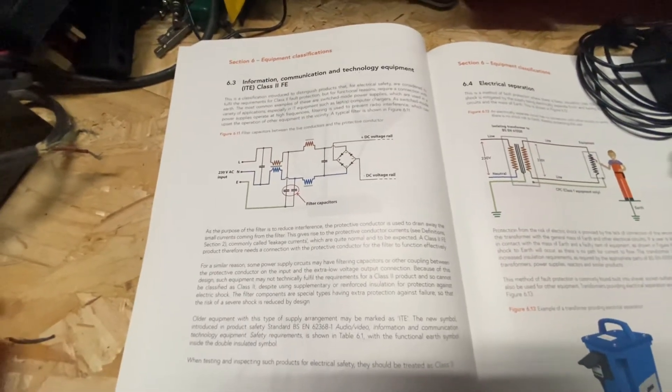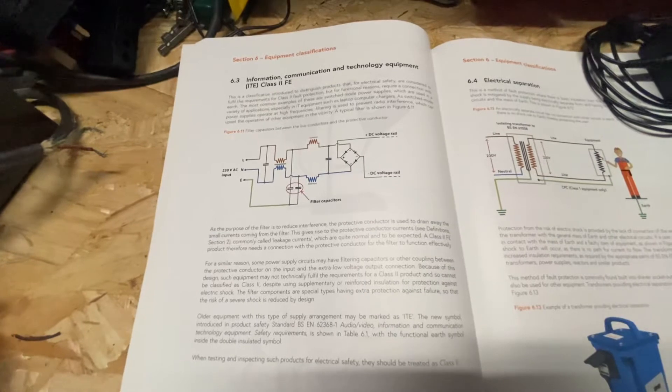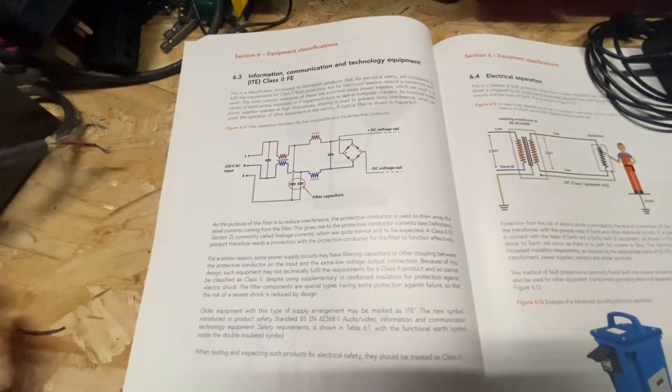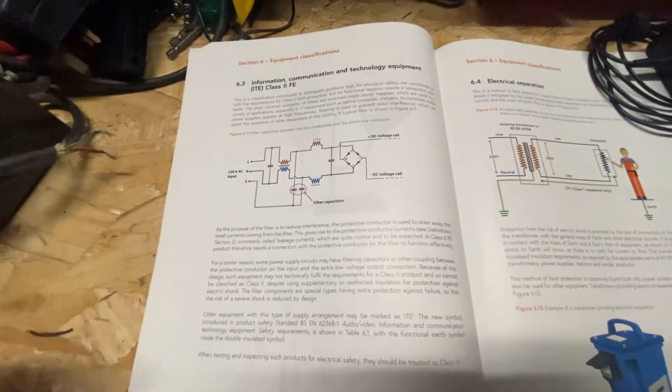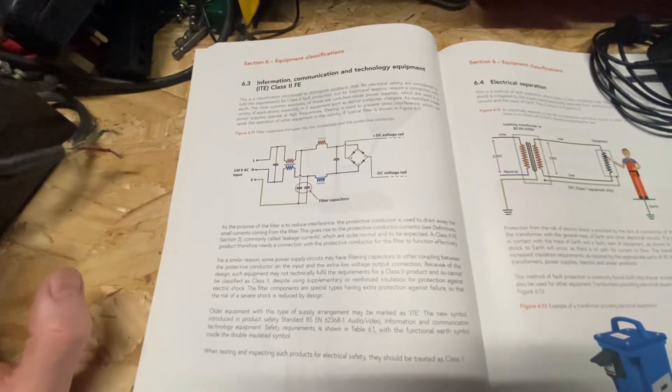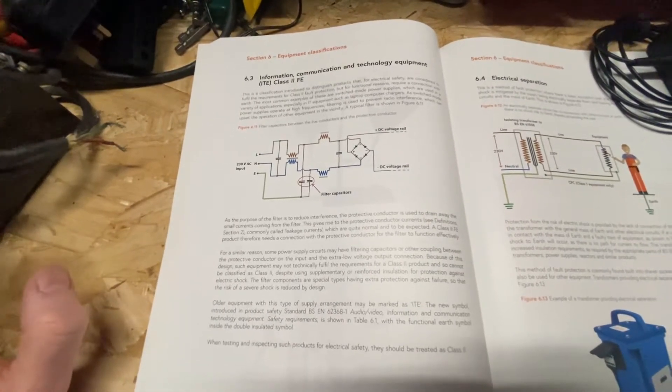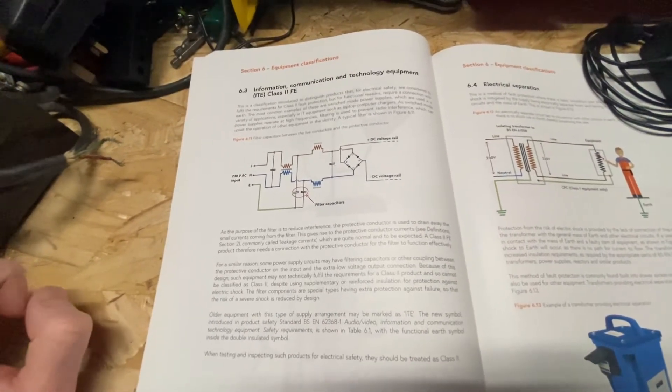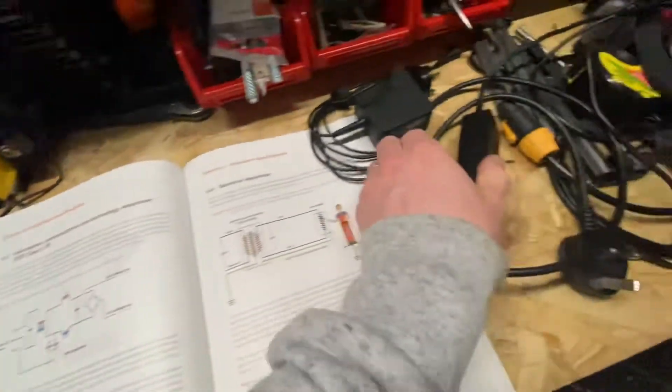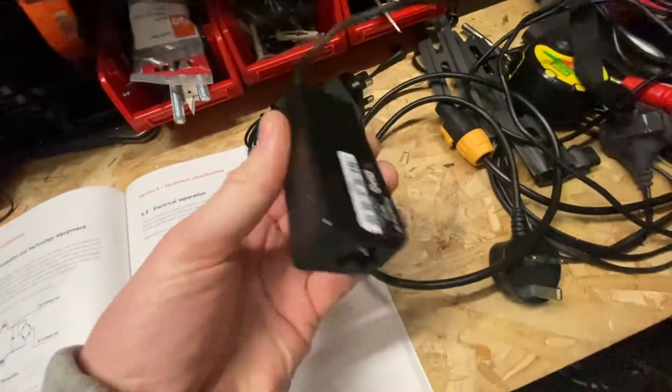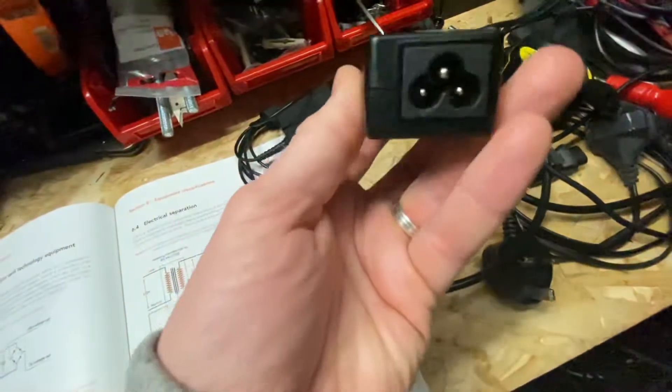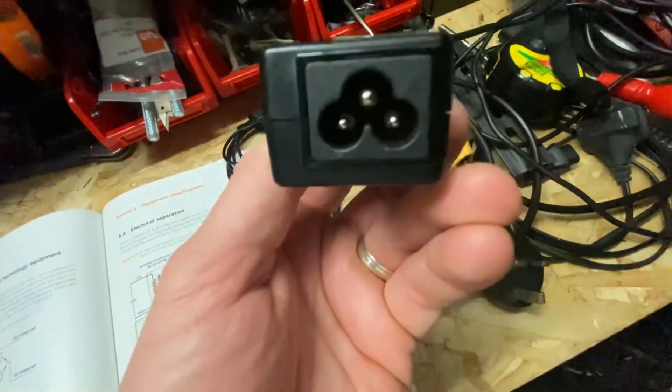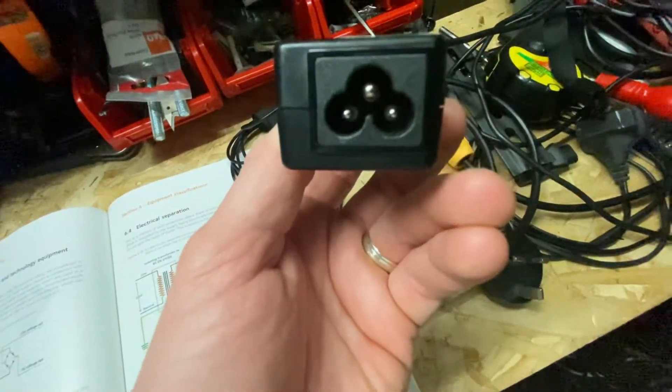So this classification was introduced to distinguish products that are considered to be class 2, but they need an earth connection for functionality. So if we go to our charger here, traditional charger here, you can see it's got the three pins: line, neutral, earth.